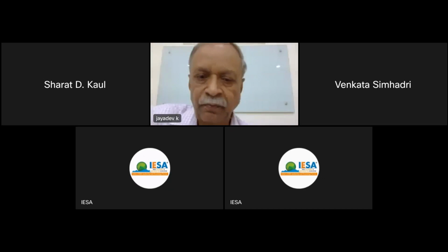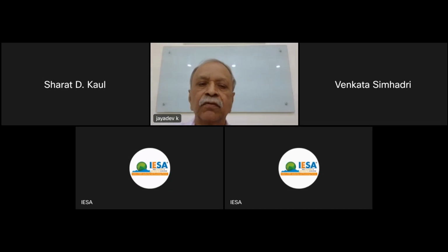Yeah, use and throw. From Dinesh, if we are not going with raised floor, can we go with regular flooring with ESD tiles, and how is the connectivity from room to room? Okay. See, normally it is not necessary to always go for raised flooring. If it's ISO 5 or ISO 6, some people require this. For ISO 5, definitely raised flooring is required. Otherwise, you can't validate it as a clean room. If there is a flat surface, you cannot call it a clean ISO 5. Non-ISO 5 clean rooms, you can go for flooring with tiles, or there may be some sheets with ESD control from room to room. You can spread it and on that you can put the wall and ceiling panels. Return air will be through the risers all along the wall.